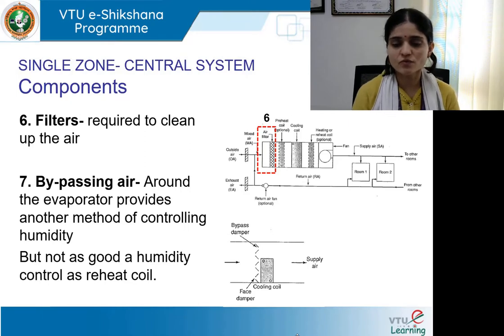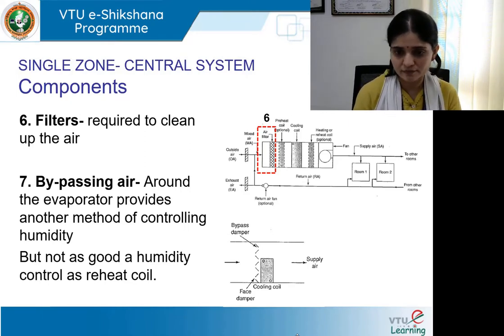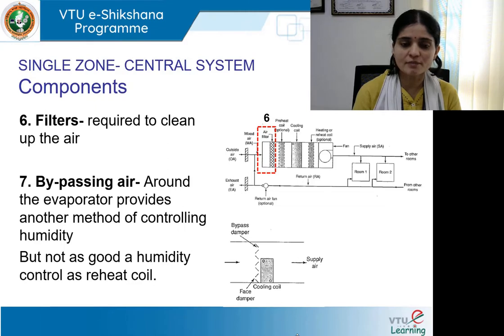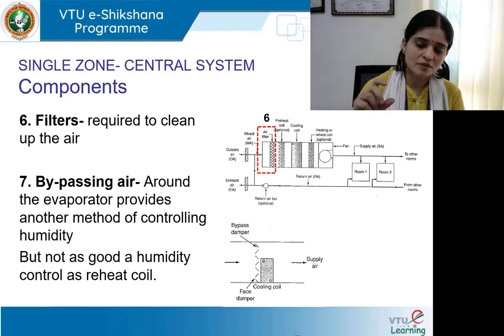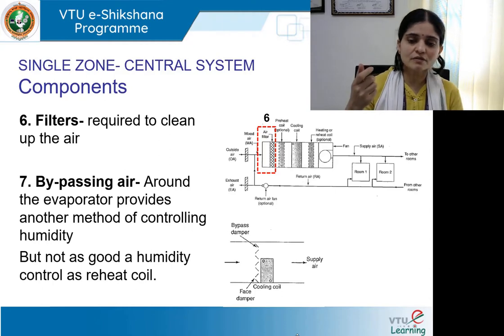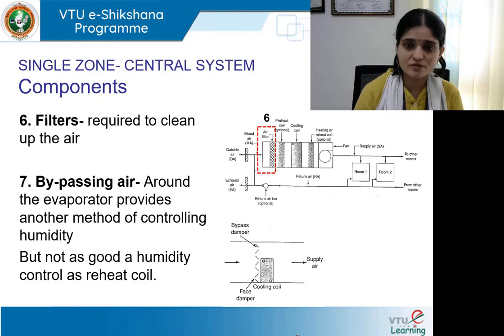Bypass air is circulated around the evaporator, which provides another method of controlling humidity in the air. However, the efficiency of controlling humidity compared to the reheat coil is limited. The bypass damper controls the amount of air passing through it. Dampers are small controlled openings which regulate the air quantity — they can be shut off when not required or regulated to let in the required quantity of air. This is all metered and monitored.